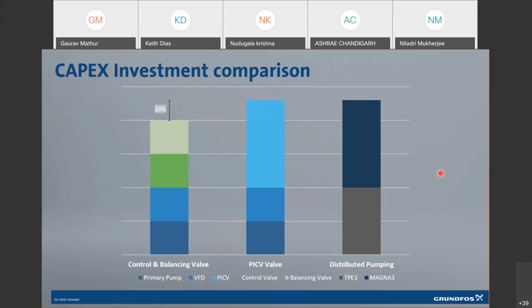But this is the OPEX part which we have discussed. It is very important for us to look at the CAPEX part also. If you see a conventional, meaning a manual balancing kind of system with a flow control device, and a PIBCV valve kind of system, when compared with a distributed pumping system, you see that a system with an automatic balancing valve is almost at par in cost with a distributed pumping system. Whereas you see a slight increase of around 20% when compared to a manual balancing system. So this is the kind of price difference at the CAPEX we are looking at.